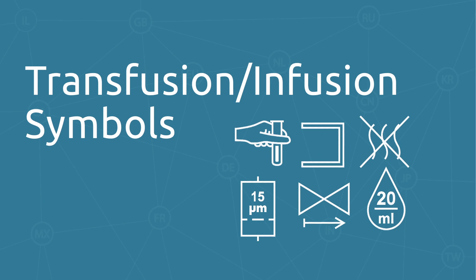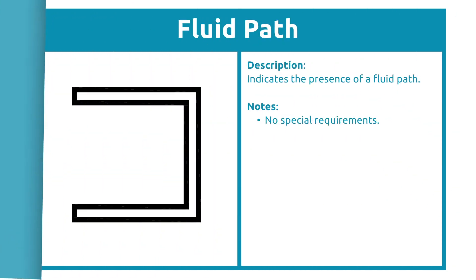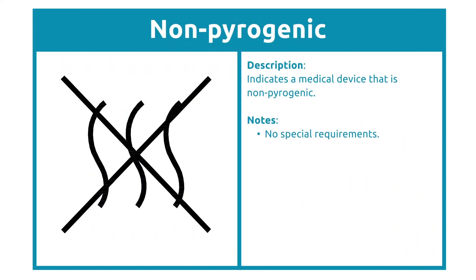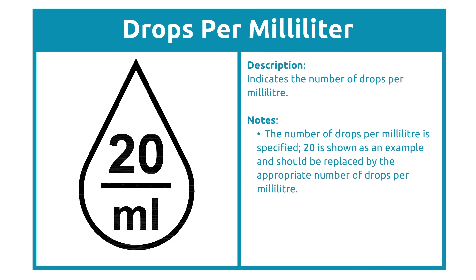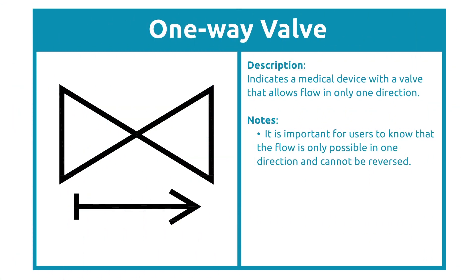Transfusion and infusion symbols are used on devices involved in transporting fluids from one place to another. The sampling site symbol communicates devices used in collecting and/or storing blood samples. The fluid path symbol identifies the flow path of fluids and can be used with other symbols to communicate more meaningful information, such as nonpyrogenic fluid path. The nonpyrogenic symbol informs that the device will not cause inflammation or induce a fever. The drops per milliliter symbol provides information on drop distribution — for example, 20 drops per milliliter, or 50 if the device distributes that amount. Another symbol communicates the filter size in micrometers; for example, a filter pore size of 15 micrometers. The one-way valve symbol informs users that the device is designed to allow fluid flow in only one direction.